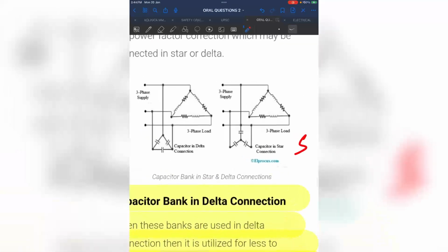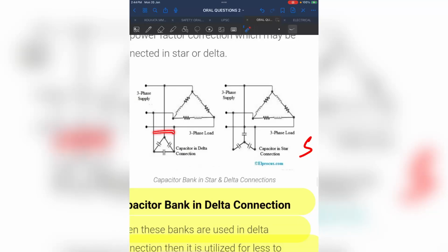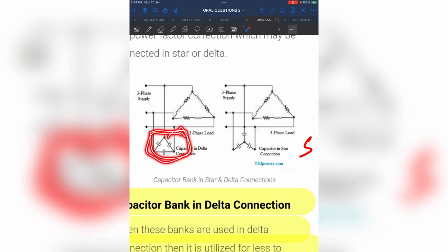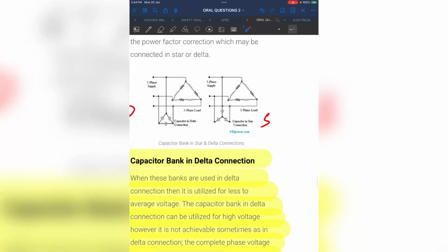One surveyor asked me to draw how a capacitor bank is connected in a circuit. So how is a capacitor bank connected in a circuit? There are these ways: a capacitor bank in delta connection, and in star connection. These are the types of configuration we use. Generally, most of the time we use the delta configuration for the capacitor banks.